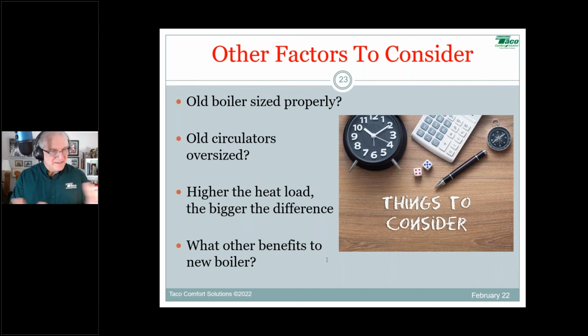It gives you a starting point. Does it include every factor conceivable in terms of efficiency? No, but it includes what we can quantify. When it comes to high efficiency boilers and outdoor reset, Dave Holdorf had a stat that just blew me away - I think over 50% of the ModCon boilers installed out there did not have the outdoor sensor installed. Don't need that problem. It boggles the mind that you'd install such a high efficiency boiler and not install the one thing that makes it work, but that's the world we live in. For the sharp service guy, there's still a lot of money to be made fixing things like that. Just an interesting concept, interesting challenge out there.